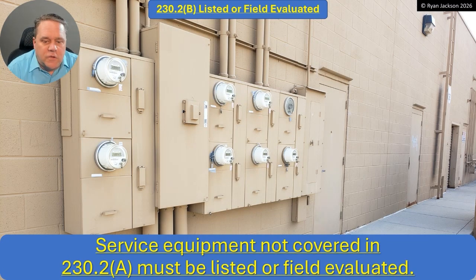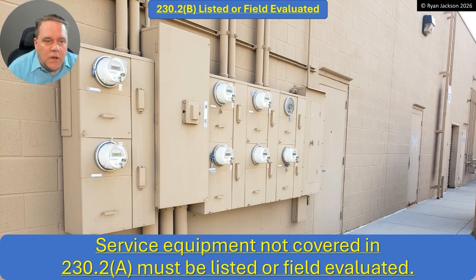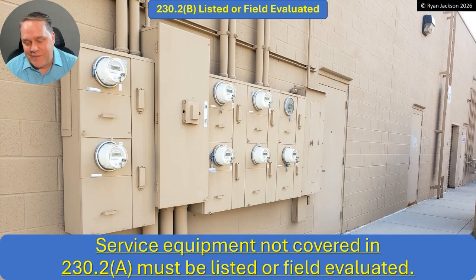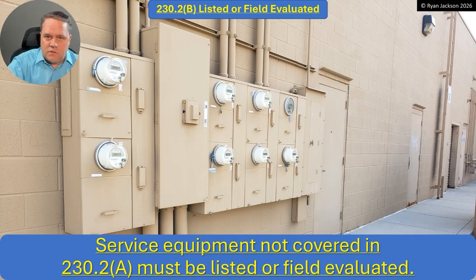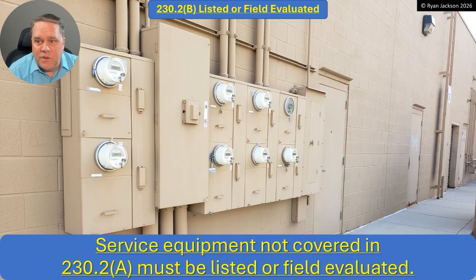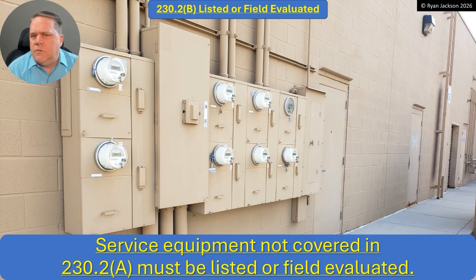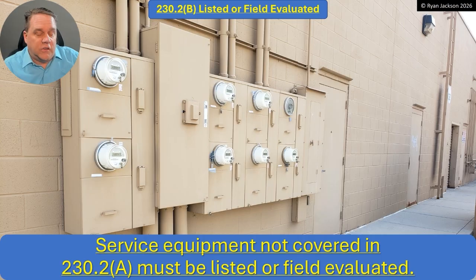Item B: listed or field evaluated. Service equipment that's not covered in 230.2A must be either listed or field evaluated. I relied on — or rather enforced — this one time as an inspector. We had an installation where the whole thing was just a bunch of motors. They installed a motor control center as the equipment, with a utility service CT can going right into the MCC. Most motor control centers are not listed as service equipment because that's a pretty unusual application — usually you're going to have a switchboard, a panel board, maybe even switchgear if it's industrial. So I did the inspection, and it was not listed as suitable for use as service equipment.